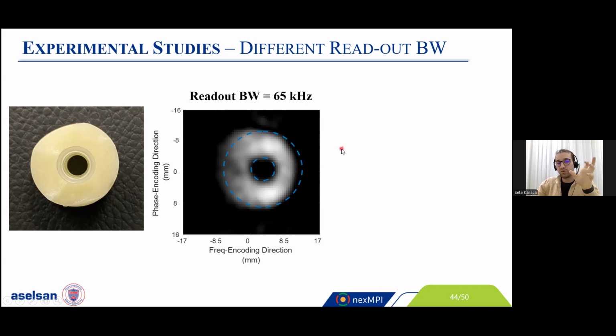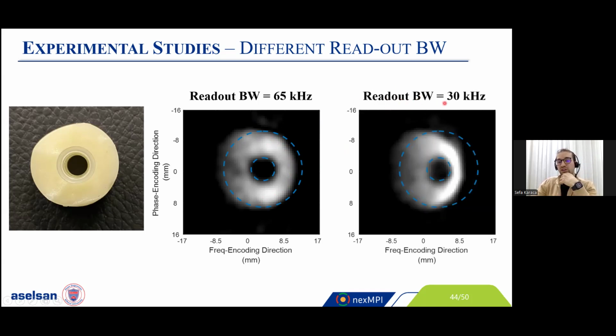If we perform low field MRI again, but only change our readout bandwidth to 30 kilohertz, as you can see, the geometric distortion artifacts because of the field inhomogeneity become much more severe. In the previous slide and the upcoming slides, we use the readout bandwidth of 65 kilohertz, but we cannot go higher than that because of our hardware limitations. To go to higher and higher readout bandwidth, you require a high gradient field strength and also a higher slew rate for your gradient coils. Our coils allow us 65 kilohertz at maximum, and we just live with it.